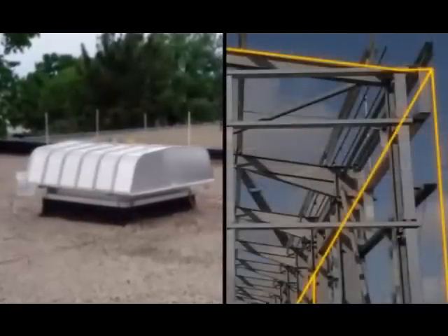There are two types of installation of lightning protection systems, concealed and retrofit. For a concealed installation, the cable is hidden within the walls of the structure. A retrofit system is installed on existing structures, with components on the outside of the structure. Both types of installation offer the same protection. However, the concealed system can only be installed on new construction.